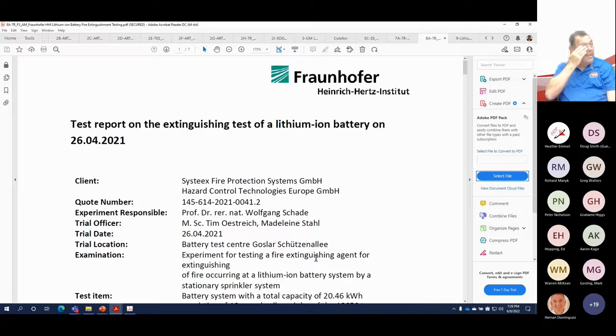The UL 9540 really addresses the propagation, the thermal runaway, the radiant heat going to the second and third racks. And you can see this testing that we have done is done on the cell level, but it's also done on the module level. So we've installed several battery energy storage systems, but we don't just go and put a sprinkler nozzle into the container because we've never tested that.